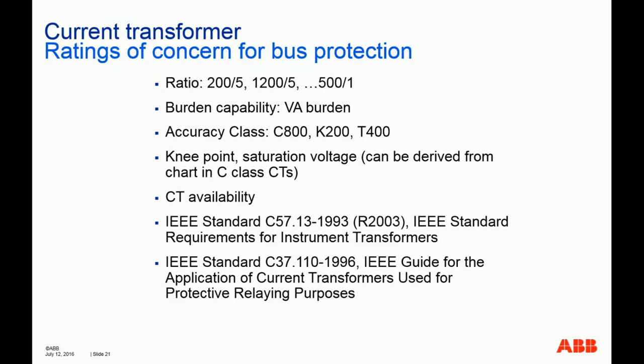in C-class CT. So what are the different types of CT classes? The C and K and the T. So the C-class CT is the standard CT most of us come across daily. Those C-class CTs mean the leakage flux is negligible. They include the multi-ratio bushing CT and window type CT, and the CT excitation characteristic can be used to determine CT performance. So basically, the CT curve we normally see and have talked about for the transformer bushing CT, breaker bushing CT, or the standalone high voltage CT, those are all considered C-class CT.